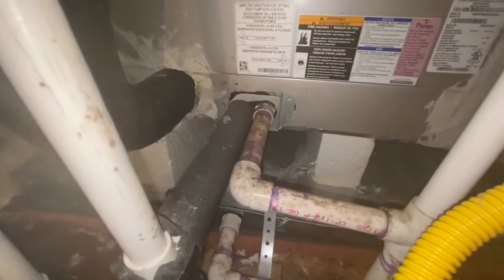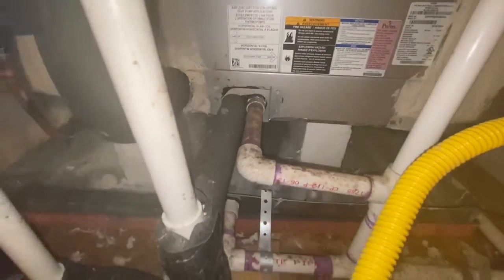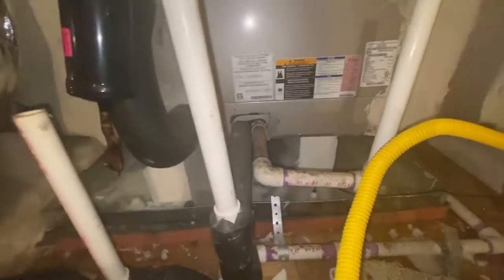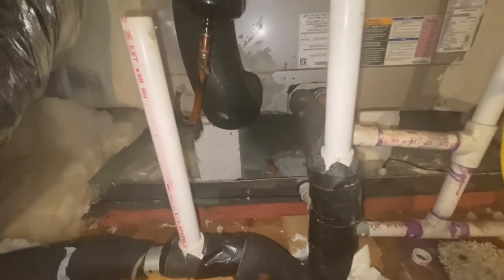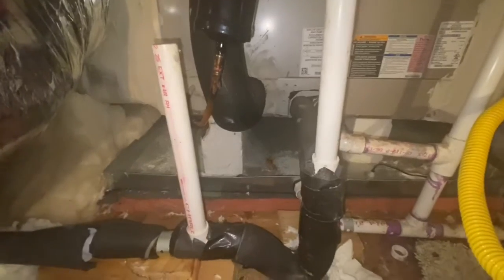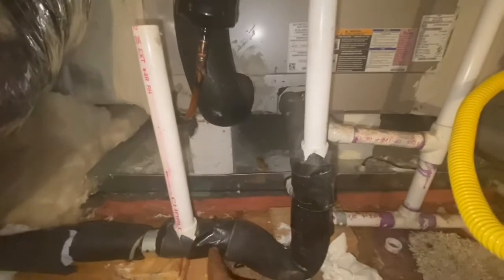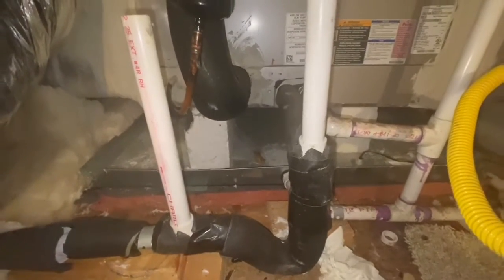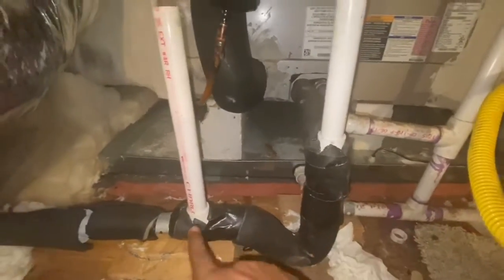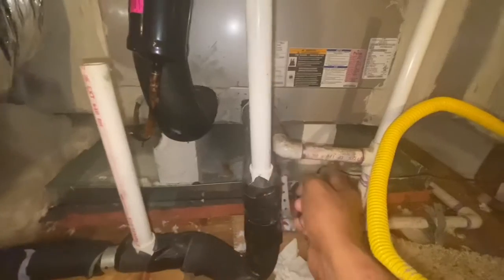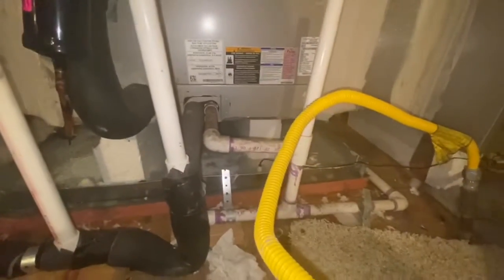Now in this case, there is nothing in the pan, but water is still coming from inside. That's the confusing part in my case. I wanted to understand why that happens. When I look at this side, the normal condensation flow has this small U here. What's really happening is that the water is not flowing through the U and going out of the actual outlet. Because the line is getting blocked somewhere around this U, the water is going out through the overflow line instead.